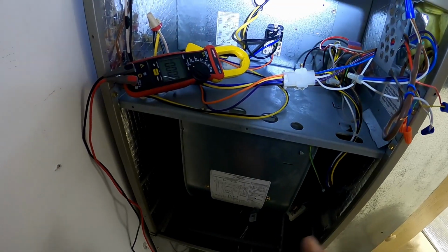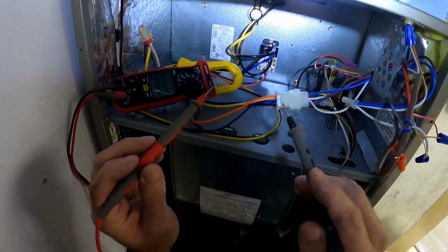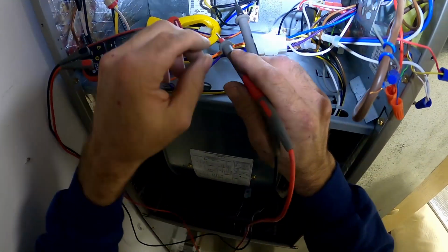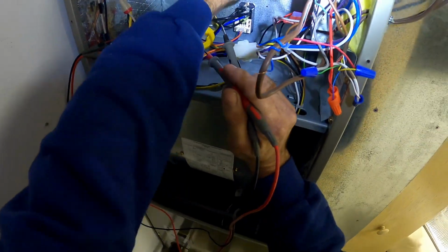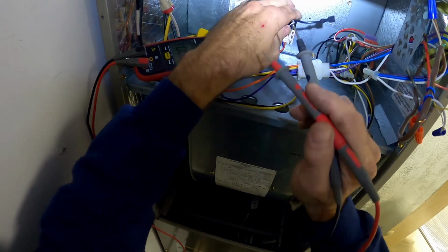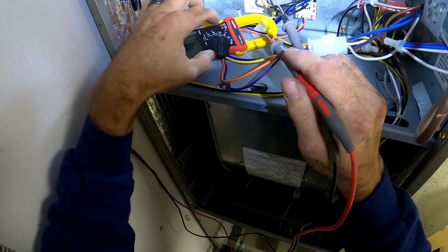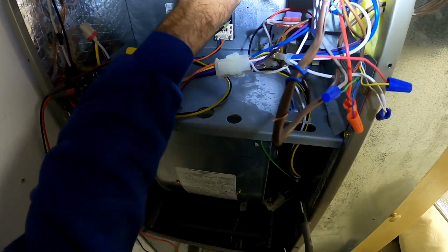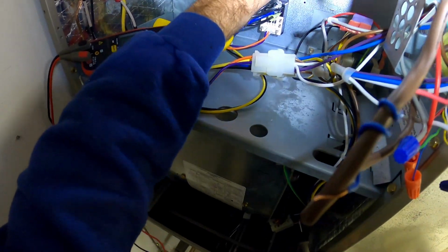And I'm thinking what happened is the motor failed, took out the strip, because the strip probably overheated and burnt up. Let's see, do I have any ohms across this thing? And absolutely not. I'm open on the strip. So the motor failed, or had an intermittent problem with the motor.